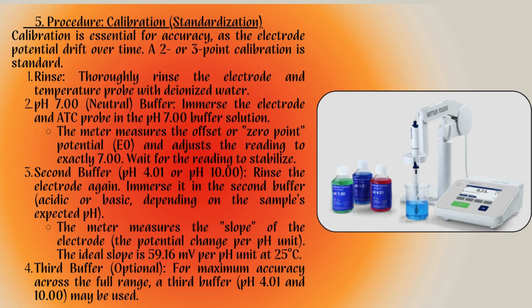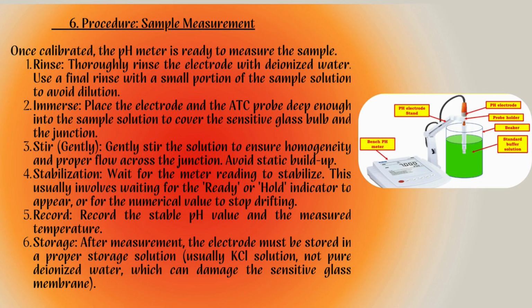The third buffer is often used for maximum accuracy across the full acidic and basic range. Now the procedure for sample measurement. Once the instrument is calibrated and the electrode slope is verified, we are ready to measure the sample. The first step is rinse and condition. We rinse the electrode again. It's also good practice to give it a quick rinse with a small portion of the sample itself to condition the glass membrane and prevent dilution.